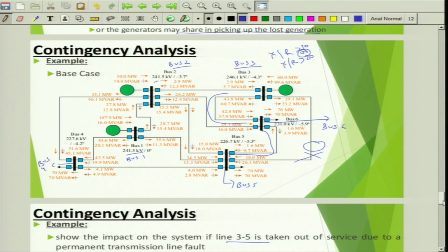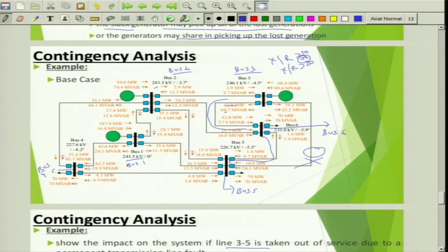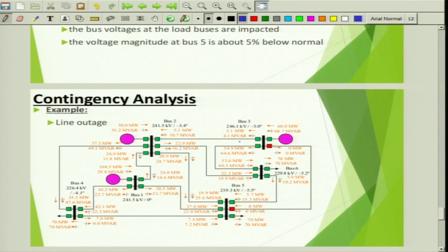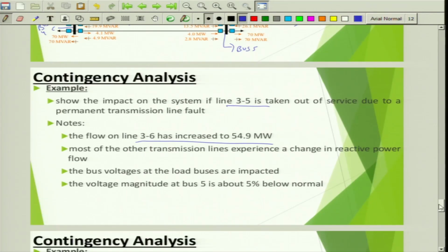Earlier you can see here this is 43.8 megawatt and 60.7 MVAR. Now that will increase. I will show you here. You can see there is an increase in flow to 54.9 and 64.6. There is an increase in active and reactive power flow because one line is gone. You can see here it is 0 megawatt and 0 MVAR, that means this is not carrying any power. Most of the other transmission lines experience a change in reactive power flow. Not only that, you can look into the pictures, other lines also have a small change in the active and reactive power flow.